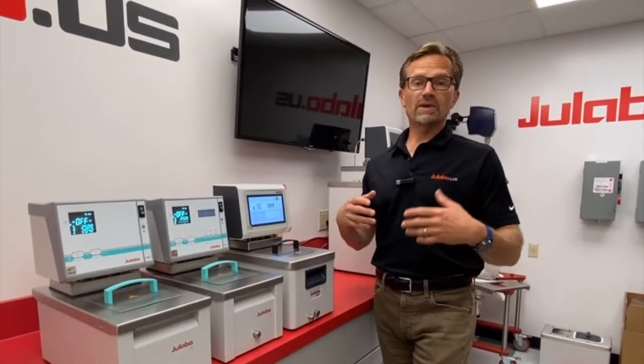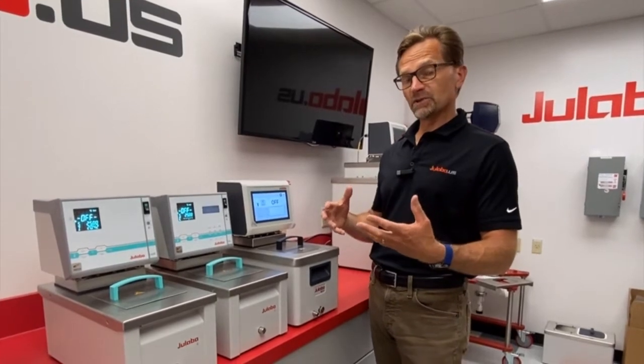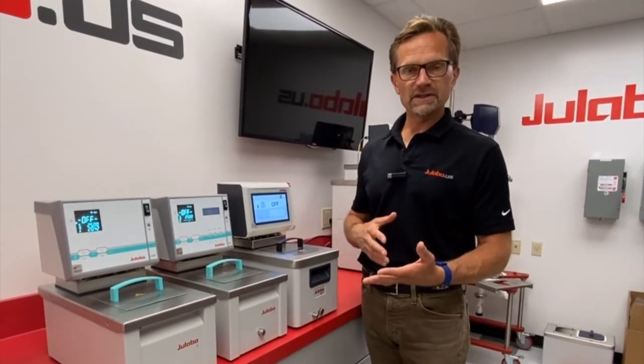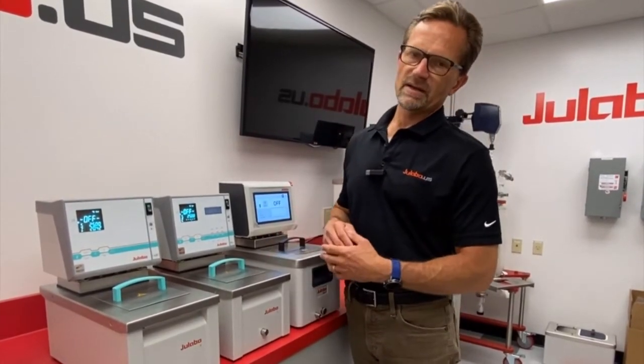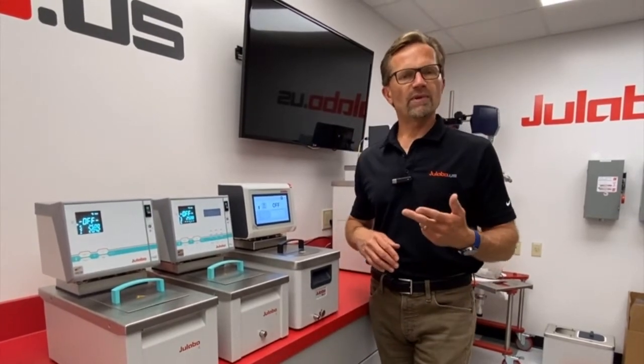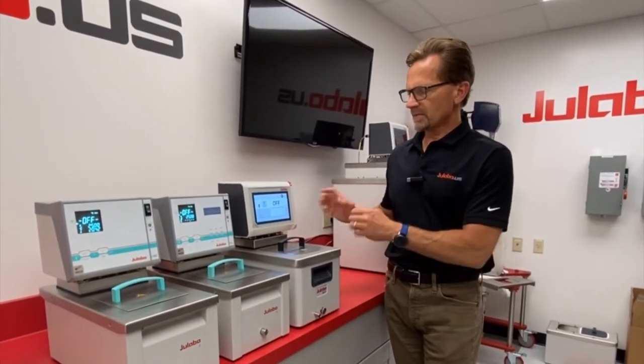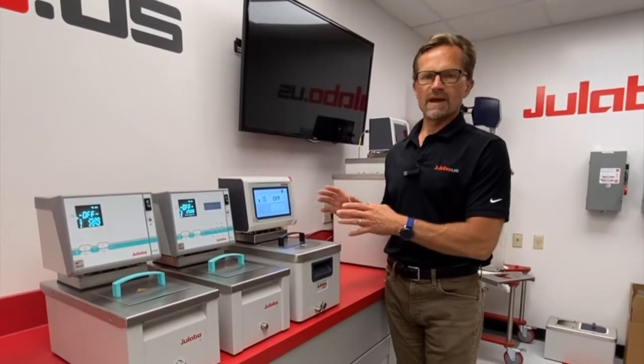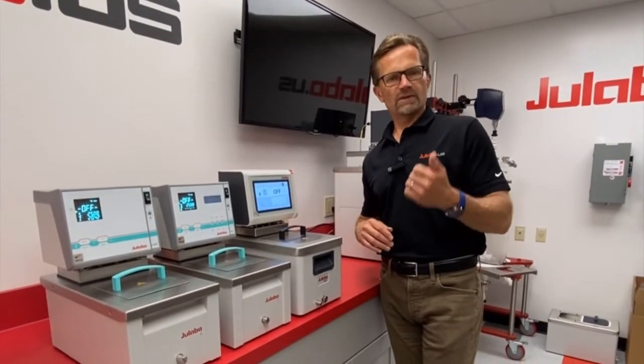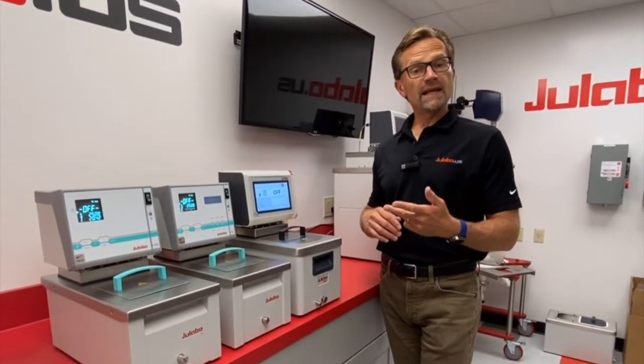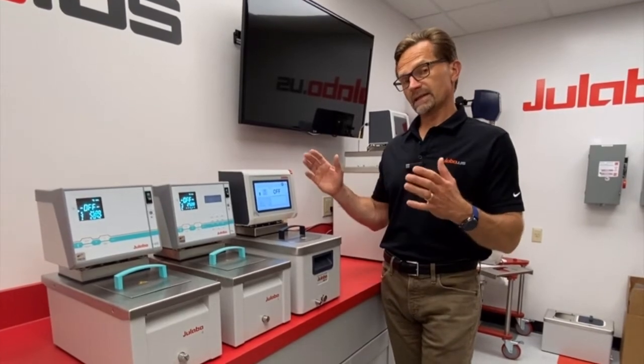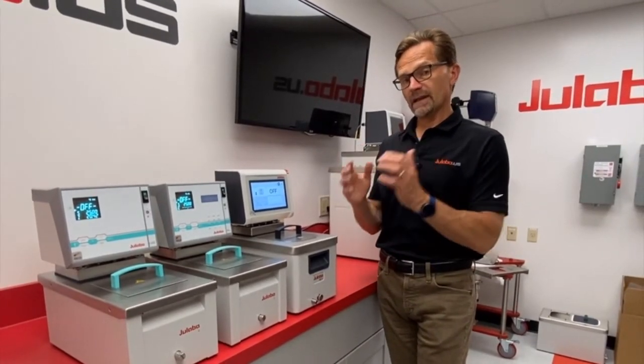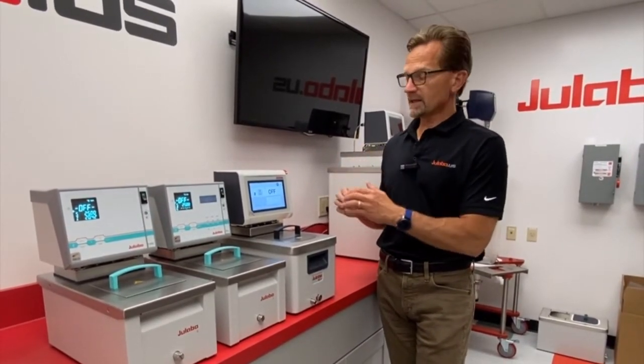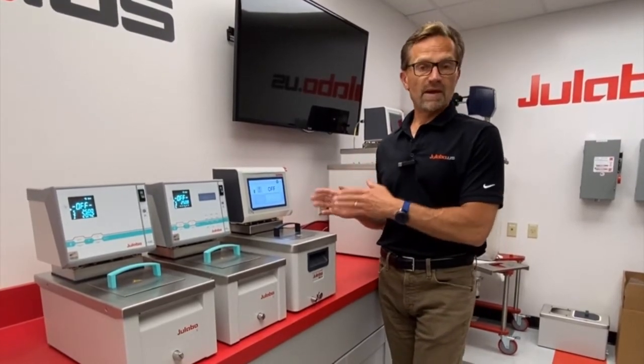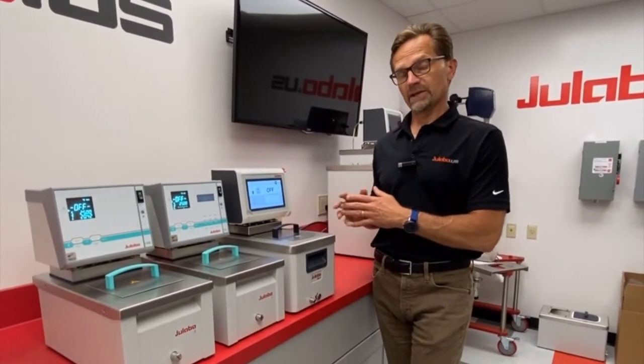For applications where you might require tighter temperature control, therefore needing calibration, the HE and the HL models have 1, 2, or 3-point calibration. On the new MAGIO MS system, you have calibration options for 1 point, 2 point, or up to 10 points. So if you have a wide temperature range, or if you want to have a lot of data points in a small range, the MAGIO MS is a better way to go with respect to a calibration curve.